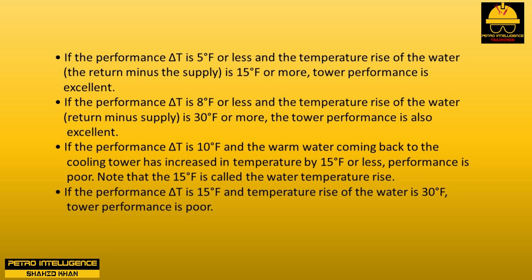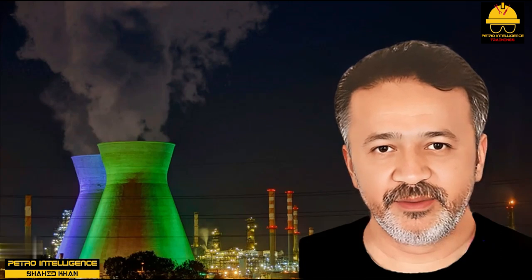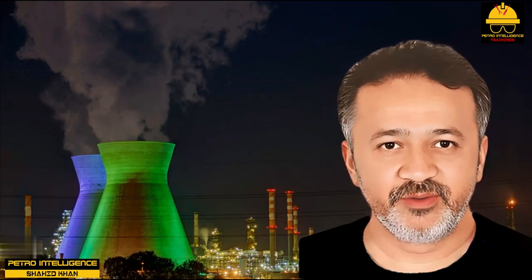Note that the 15°F is called the water temperature rise. If the performance delta T is 15°F and the temperature rise of the water is 30°F, tower performance is poor. In older induced draft wooden cooling towers, a common problem is that the wooden slats have broken up — there is usually an access inspection door at the base of the cell. Often the water distribution holes are plugged or there are large holes broken into the deck. Water is not supposed to overflow around the outside of the cooling tower. On some cooling towers, the fans are driven by belts which can slip, or the fan blade pitch is set too low — less than 15 degrees; the maximum is 23 degrees.